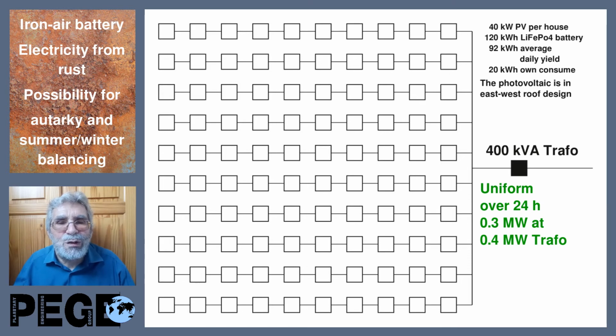And when a day has more photovoltaic yield than 133% of an average day, the additional power goes to the iron-air batteries. And because we need 2,500 kilowatt hours to charge 1,500 kilowatt hours of iron-air batteries, this happens in all the summer, and at the end of the summer the iron-air batteries should be fully charged and can deliver the energy back in the winter half year.